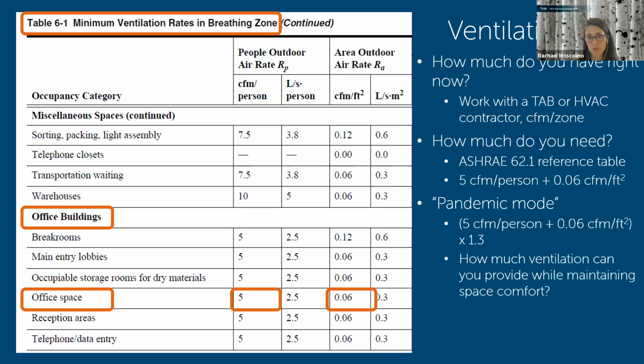And this is what we're doing with our customers. We're helping them evaluate what they have, compare it to what they need, and then look at how ventilation plays into their overall indoor air quality strategy and decide if they want to increase that ventilation for a subset of time. Something you may be hearing is this whole idea of a pandemic mode. So the idea that a building reacts differently when there is an outside environmental impact that could be impacting the occupants. And if we want to put a number on that pandemic mode for ventilation, some people are saying 30% more than that ASHRAE minimum.